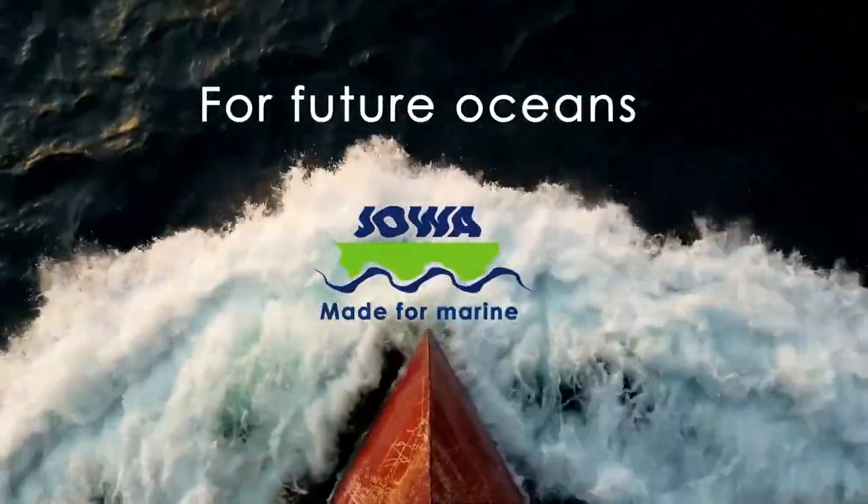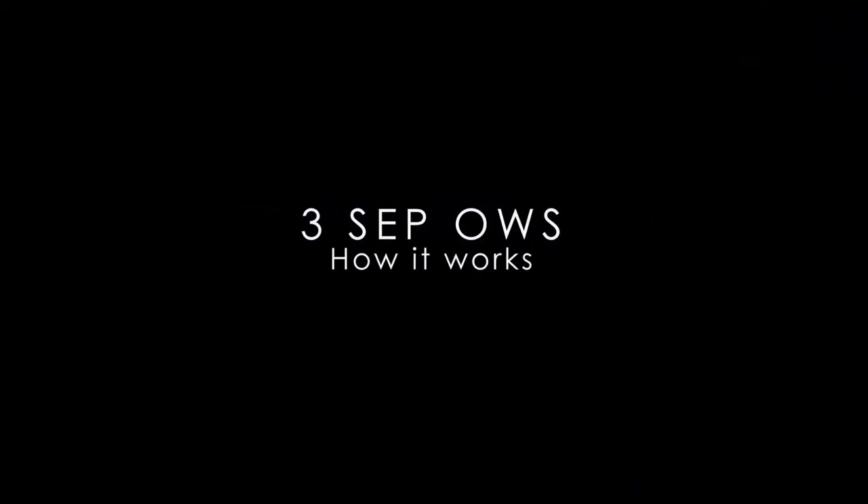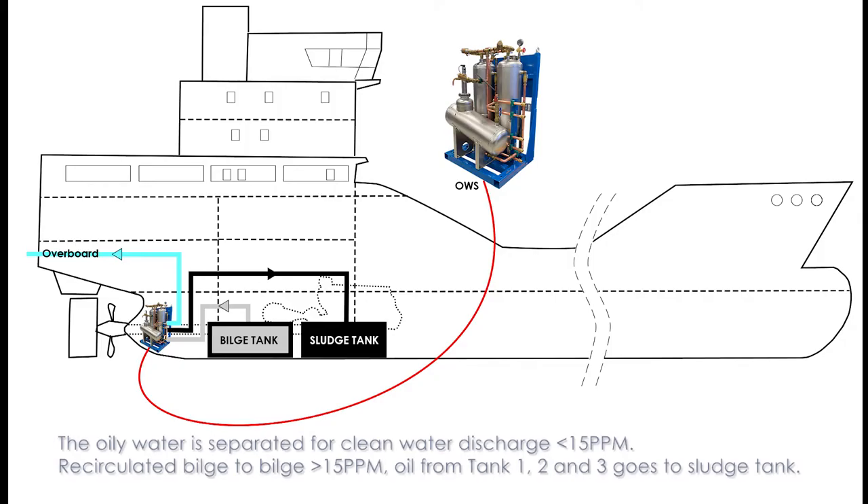For Future Oceans — JOWA, made for marine. The 3 SEP OWS: how it works. The oily water is separated for clean water discharge below 15 ppm. Above 15 ppm, bilge water is recirculated back to the bilge tank. Oil from tanks 1, 2, and 3 goes to the sludge tank.